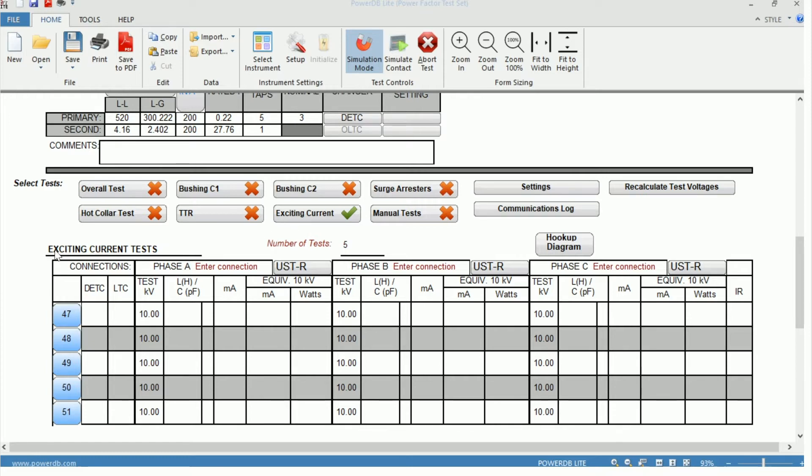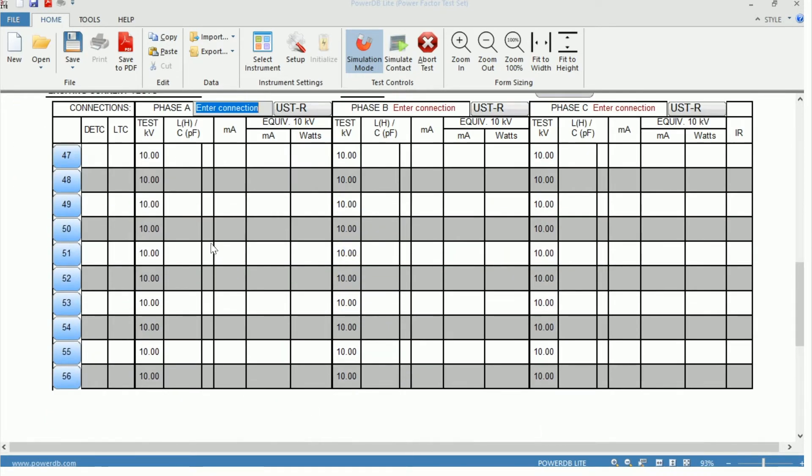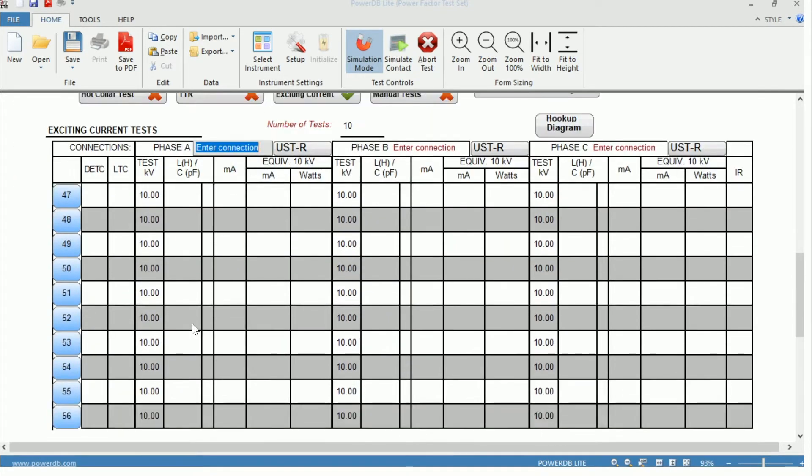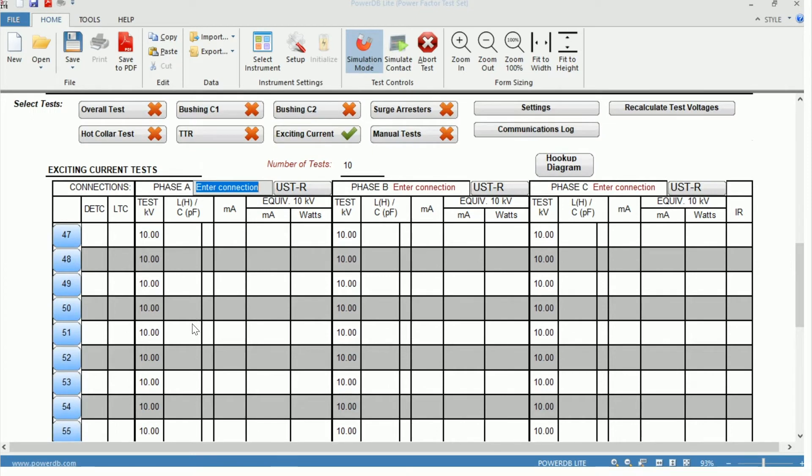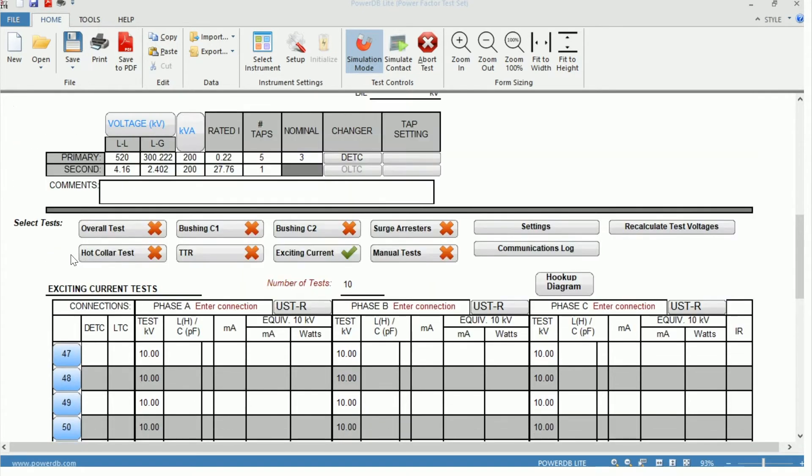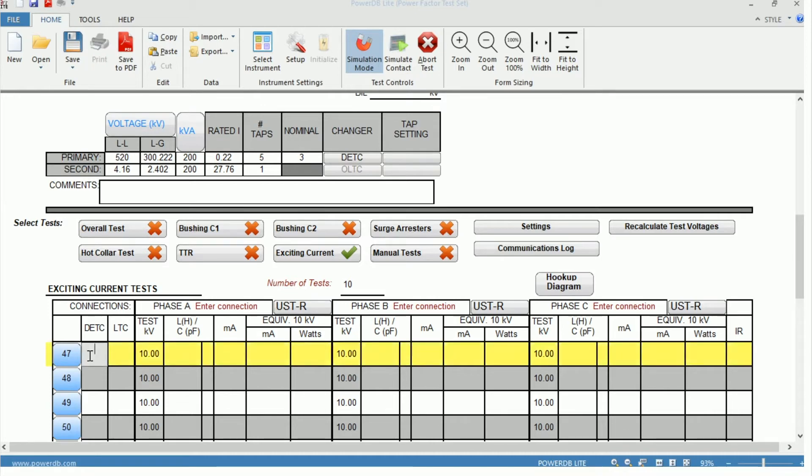Looking at the excitation current test, we can see initially the number of tests defaults to 5. If we wish to add more tests, we can simply come in and type in, hit enter, and it will populate with more fields. Looking over at the left-hand side, we can see columns for DETC and LTC. These are to document which tap you're on when performing the test. We can see that we don't have an onload tap changer in this example, but we have 5 taps on our de-energized tap changer where our nominal is tap 3. So we'll go ahead and just put in tap 3 as if we're testing on our nominal.